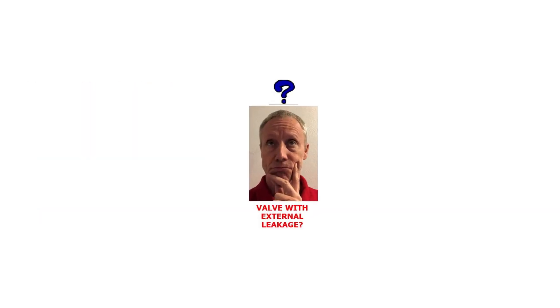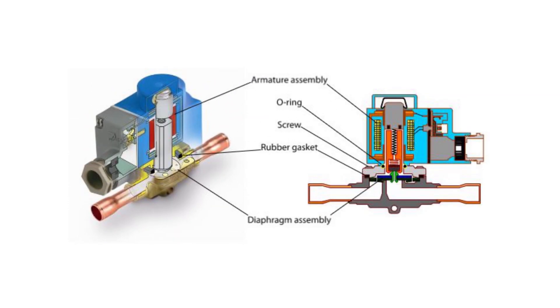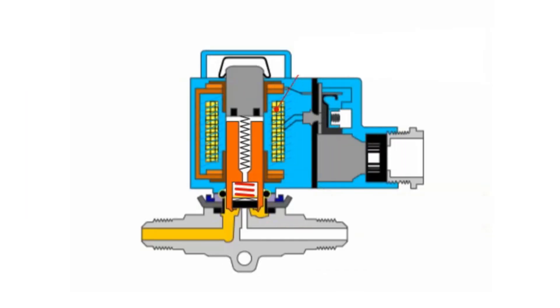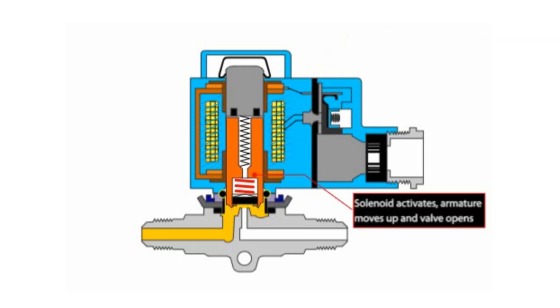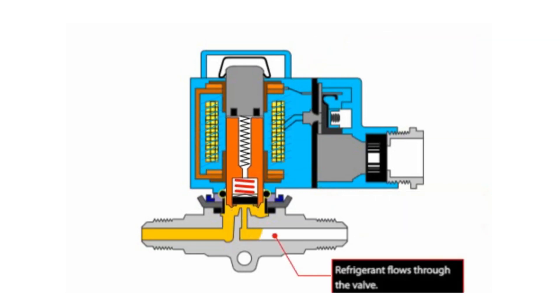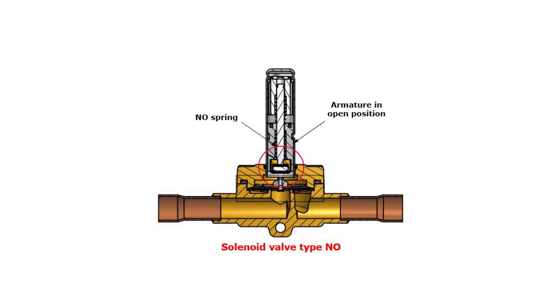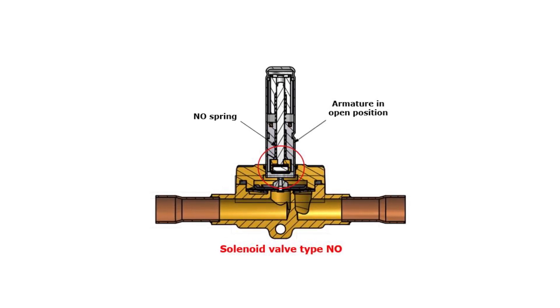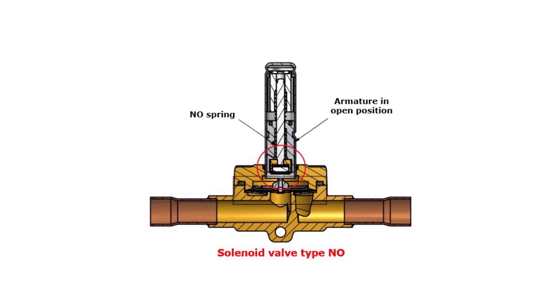Now let us look at the solenoid valve failure where the valve has external leakage. This valve failure is related to both a solenoid valve type normally closed, called NC, where the valve is forced closed by a spring and is open when energizing the coil, as seen here. And valve type normally open, called NO, where the valve is forced open by a spring and is closed when energizing the coil, as seen here.